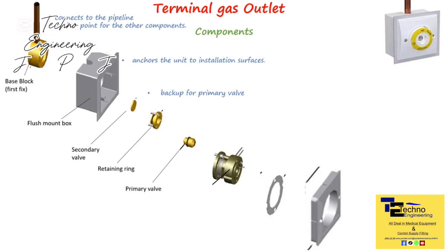The primary valve operates as an automatic shut-off valve and primary check valve, allowing gas flow upon insertion of a male probe and automatically closing when disconnected. Lastly, the secondary fix holds together the valves of the terminal unit, with gas labels imprinted on the label panel, while the entire unit is covered and sealed by the flush fascia.